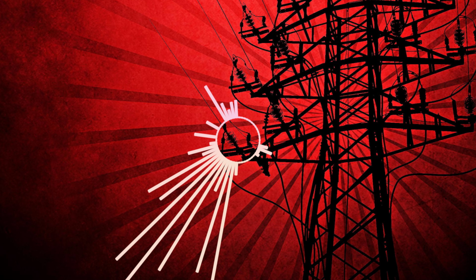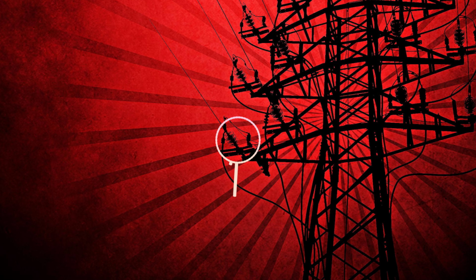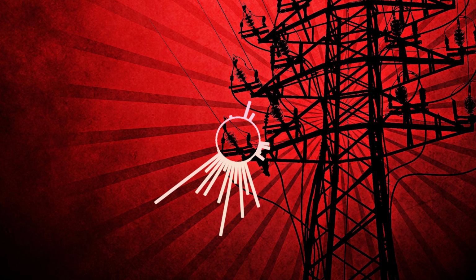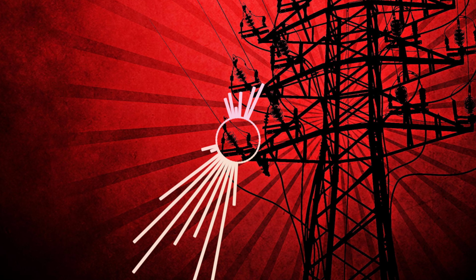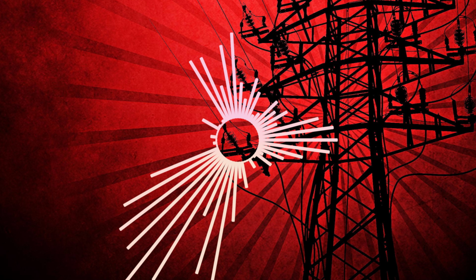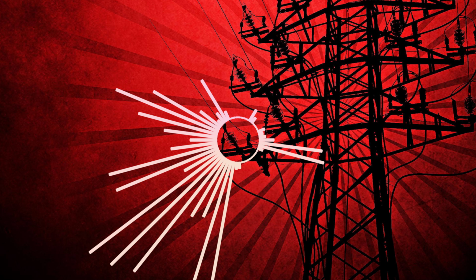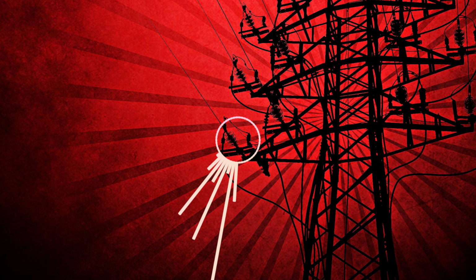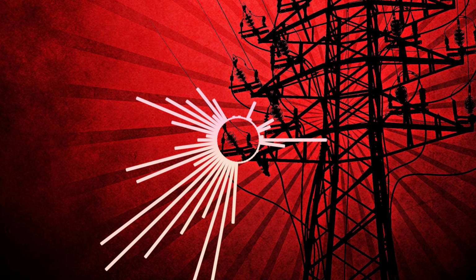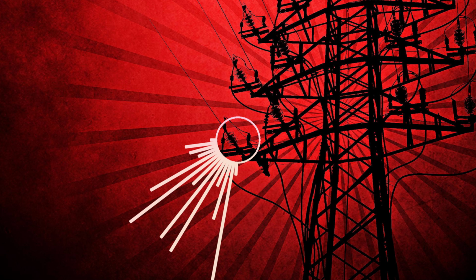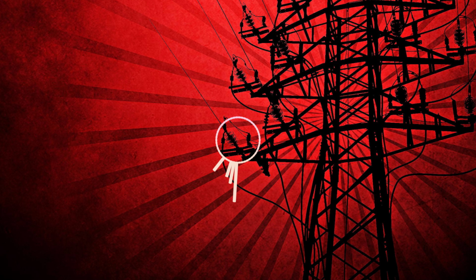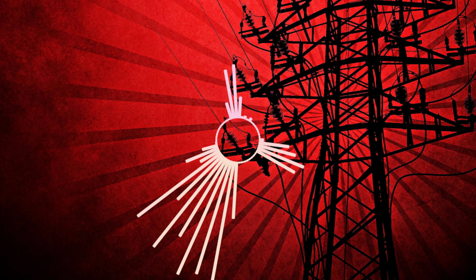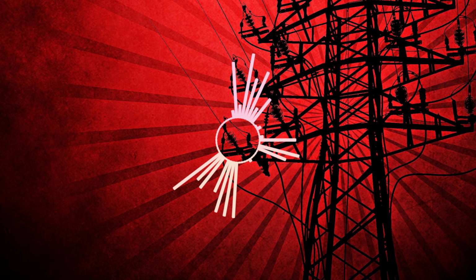So why was this article added to the code? Electrical safety incidents involving CTs go back decades. Engineers and electricians were getting injured or equipment was being destroyed just because someone opened a CT circuit while it was live. So NEC 110.23 was introduced to create a universal, enforceable rule to prevent these accidents. It's one of those rules that may seem technical on paper, but in practice, it saves lives and prevents costly damage every single day.